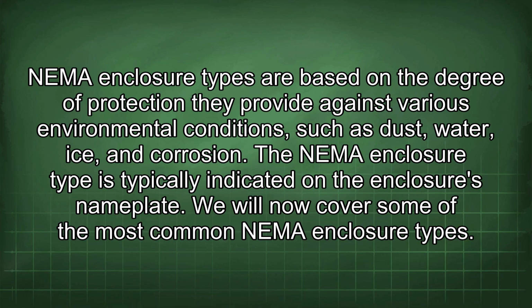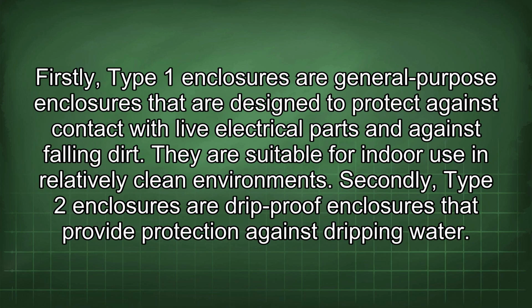We will now cover some of the most common NEMA enclosure types. Firstly, Type 1 enclosures are general-purpose enclosures that are designed to protect against contact with live electrical parts and against falling dirt. They are suitable for indoor use in relatively clean environments. Secondly, Type 2 enclosures are drip-proof enclosures that provide protection against dripping water.